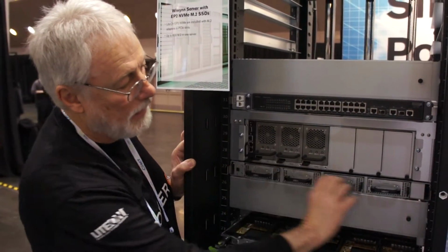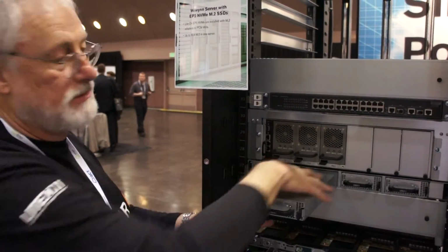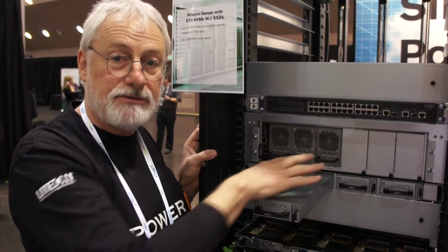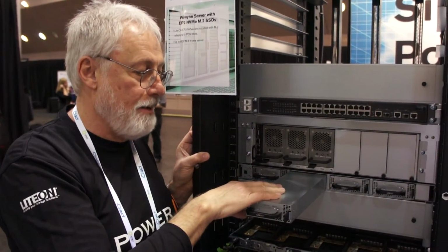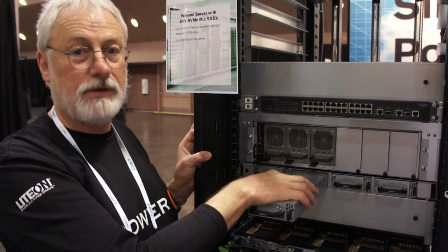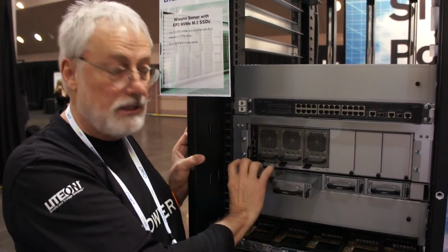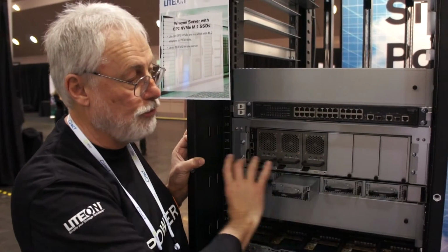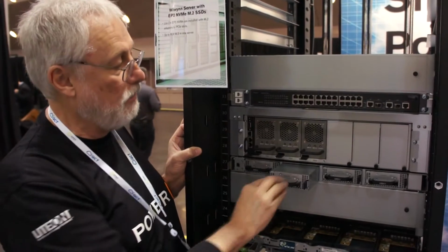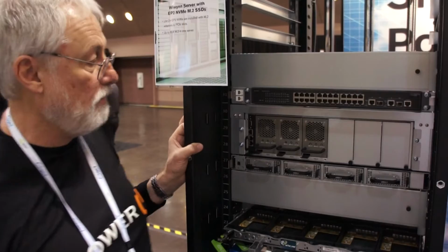Here you see a shelf that has 4 slots. Each one of these slots would contain a battery module. We have a battery module based on lithium technology that provides 1.75 kilowatts at the battery module level for 3 minutes of runtime. And if you put this in a 4-slot shelf, then that would give you 7 kilowatts of battery runtime in a 1U space. And these, of course, can be added. So 2 of these would give you 14 kilowatts, giving you the power backup for the 12.5 kilowatts here.